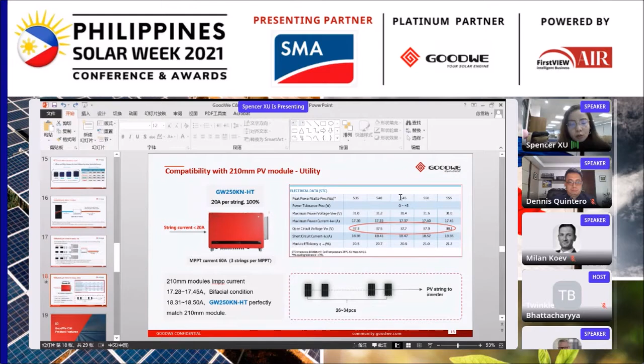While for the utility projects, we have the special version KNHT, as we've mentioned. The string current of the KNHT is 20 ampere with a 3-string design. Most clients may have the concern whether they need an external fuse to prevent the 2-string current from backfeeding to the 1-string. Well, the KN still uses the no fuse design to solve this problem, but it is equipped with an intelligent DC switch, which can automatically trip when an overcurrent failure occurs. This DC switch can receive the trip signal from the inverter DSP to shut down the DC circuit when an emergency happens. So we can say that our new model is also perfectly matched to the 210 millimeter modules.